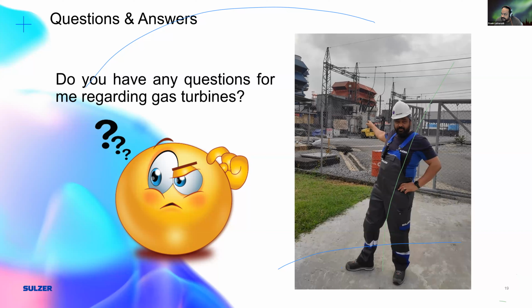What we would call an E-class machine - they have years of proven experience. If you want to go with Siemens, you would have the V94.2. If you want to go with GE, you would have the Frame 9s. If you want to go with Alstom, you have the 13E2s. These are the kind of turbines I'll be looking at, because the return on investment is actually quite short. The maintenance is easy, you can have extended lifetime cycles, and you have a lot of manufacturers who are able to provide spares - case in point, Sulzer, they are able to refurbish parts for you. So if you settle for an E-class, you should be on a good way.